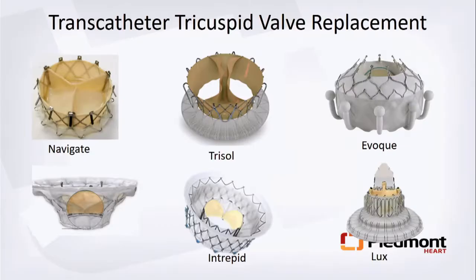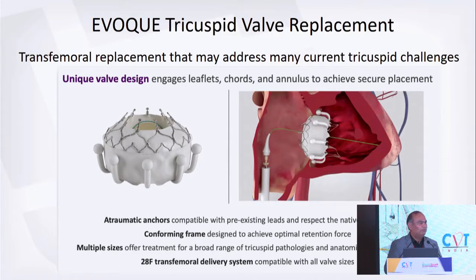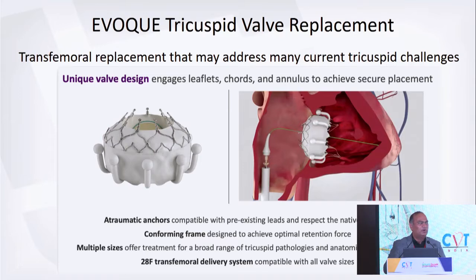I'm going to show a case of EVOQUE — the front runner in tricuspid replacement. It is an Edwards LifeSciences prosthesis: a nitinol frame, self-expanding, with nine atraumatic anchors that capture the leaflets of the tricuspid valve so excessive oversizing at the annular level is not required, though some oversizing helps in anchoring. It comes in three sizes: 44, 48, and 52mm. It's a 28 French transfemoral delivery system with a bovine pericardial tri-leaflet valve.